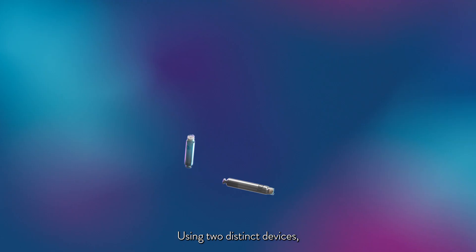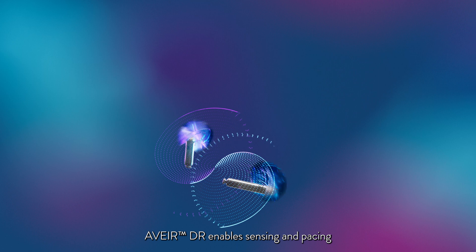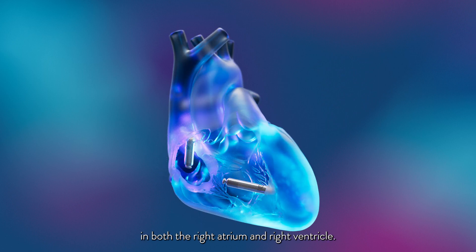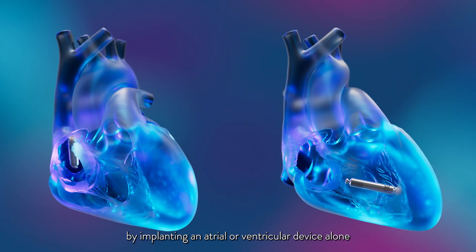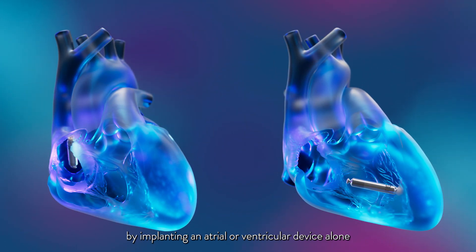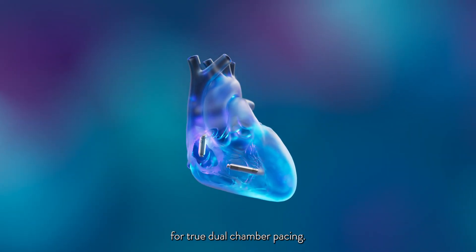Using two distinct devices — one designed for the right atrium, the other for the right ventricle — Aveir™ DR enables sensing and pacing in both chambers. Continuous atrioventricular synchrony, or beat-to-beat synchrony, is achieved by proprietary i2i, or implant-to-implant, conductive communication using the patient's bloodstream. Aveir™ DR can be tailored by implanting an atrial or ventricular device alone, or both devices combined for true dual-chamber pacing.